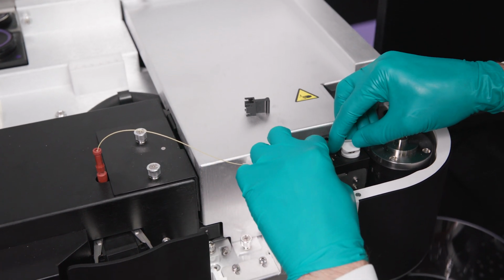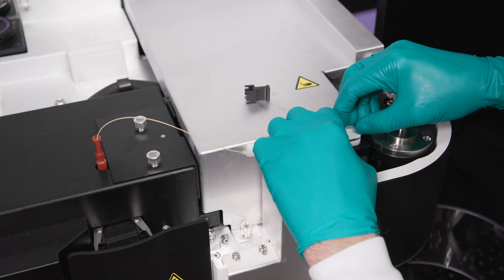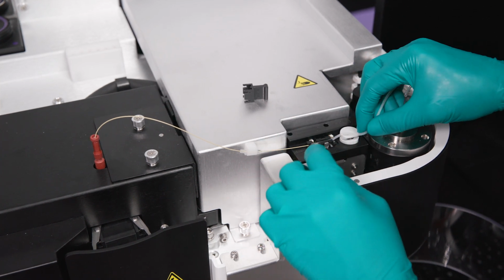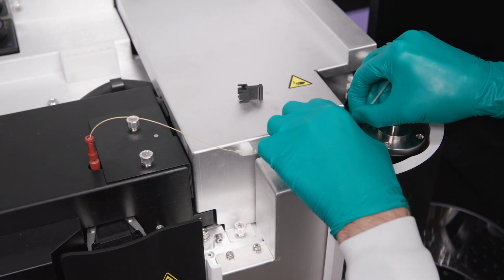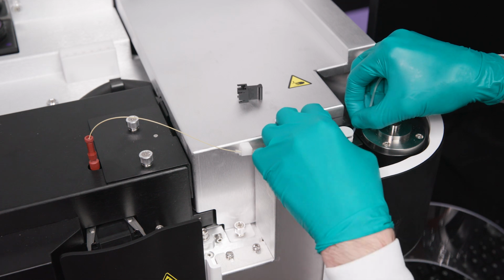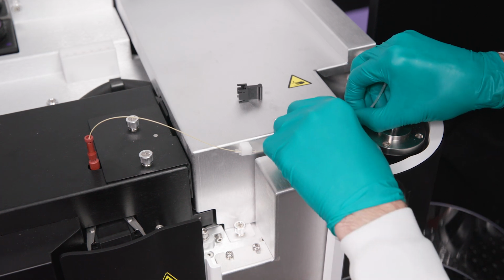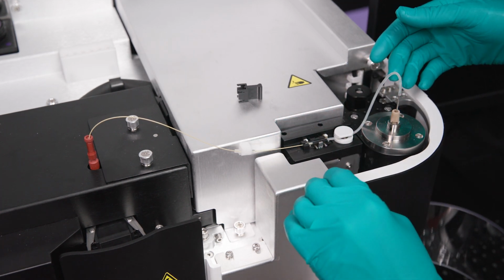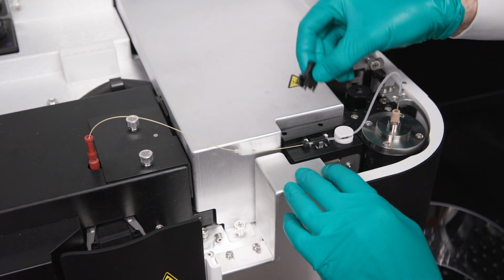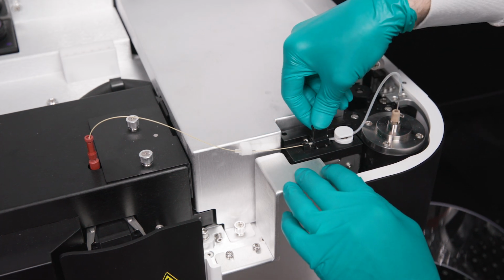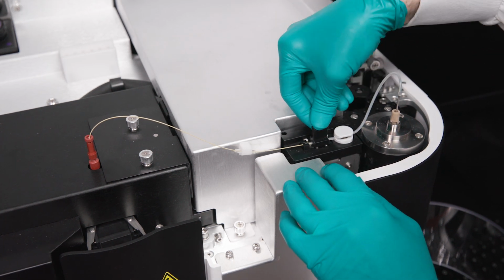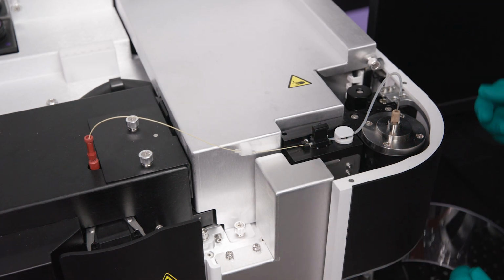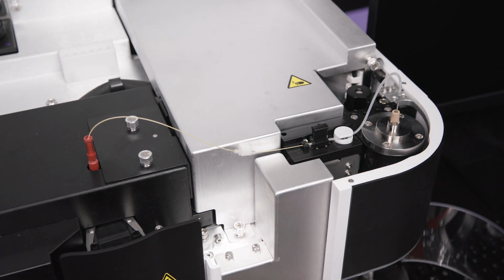Place the line back within the bubble detector. And make sure it snugly fits into the pinch valve so that when the pinch valve is closed, it will stop the sample from running. Replace my cover to the bubble detector. And you've replaced your sample line and probe.